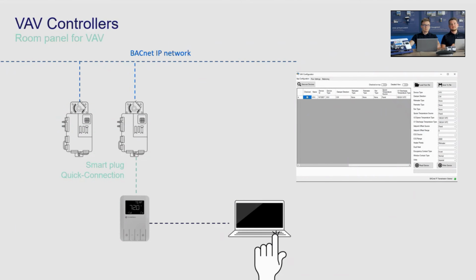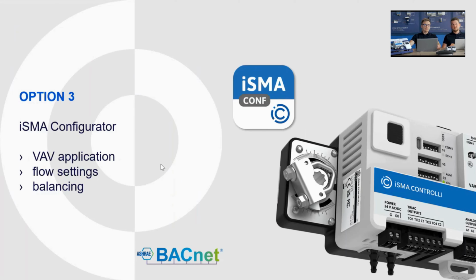Okay, let's go further. And this is the second option I mentioned. So by accessing the CP control point unit through the USB-C port, we can, on our laptop, open the iSMA Configurator and freely configure the application directly using the same methodology you would use on the panel itself, but with a nice prompt interface that will allow you to speed up the configuration. Option number 3 is the iSMA Configurator software. And this software allows you to make the application configuration, flow settings, and balancing. So exactly the same options that you have available in the CP panel.